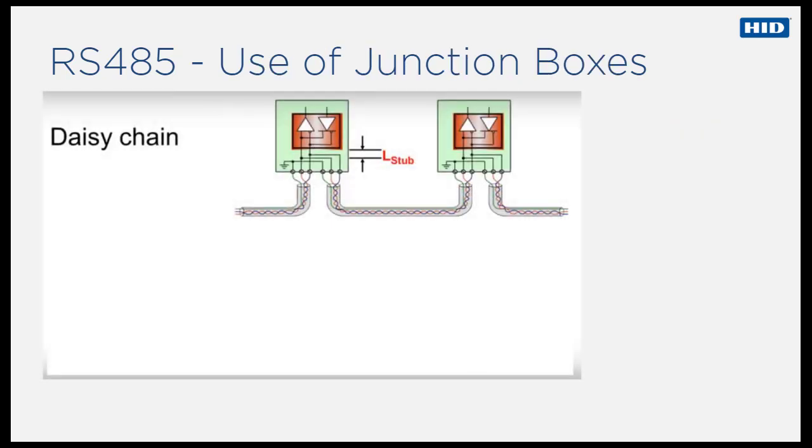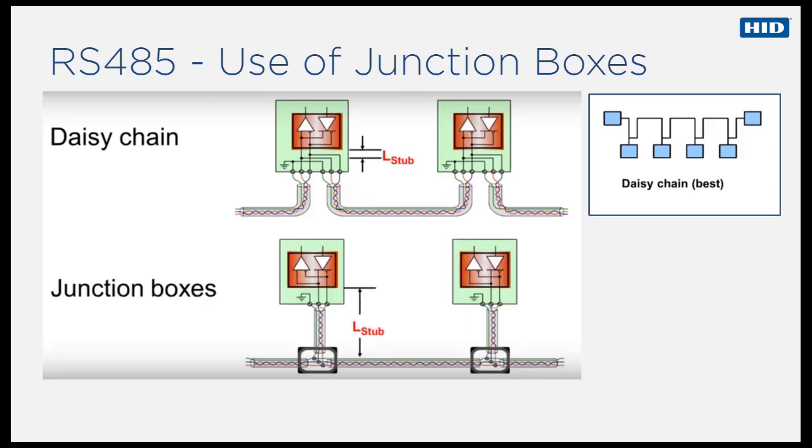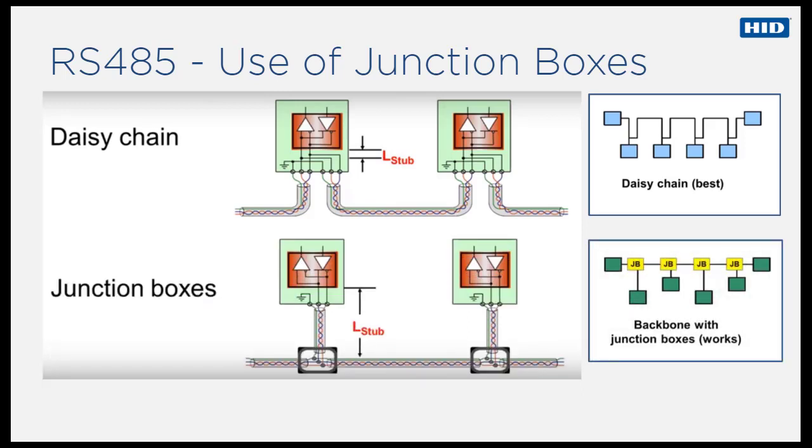Star type connections are not allowed. Daisy chain topology with direct connections to readers is recommended. Daisy chain topology using junction boxes is not recommended, but backbones comprising of junction boxes can be made to work if the stub length is kept as short as possible.